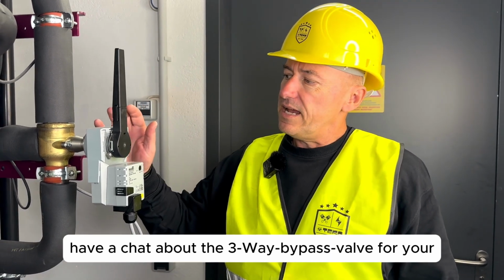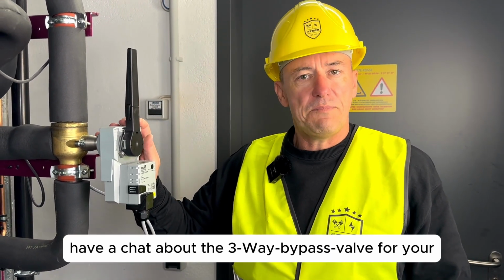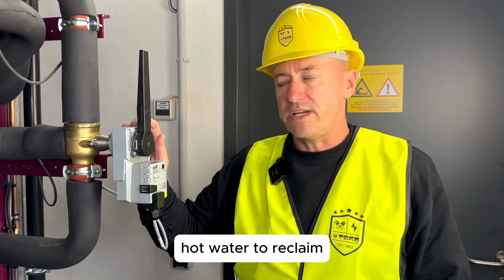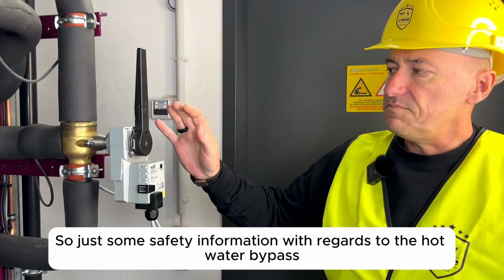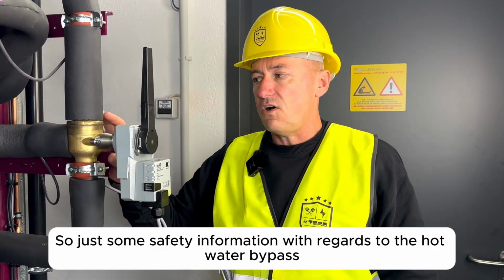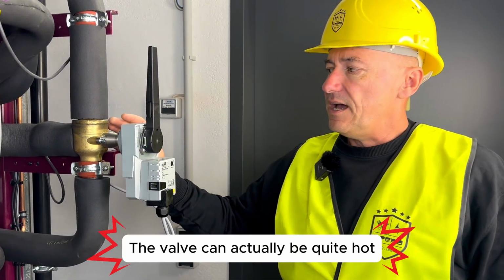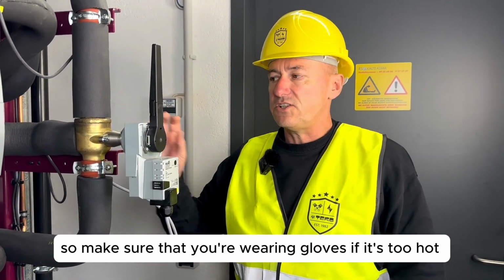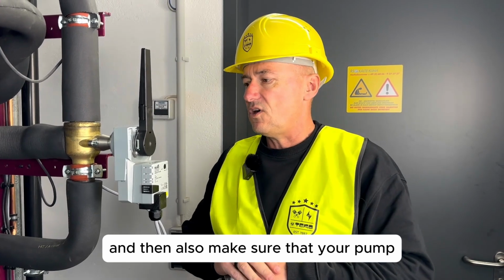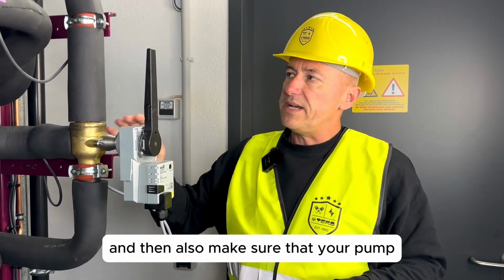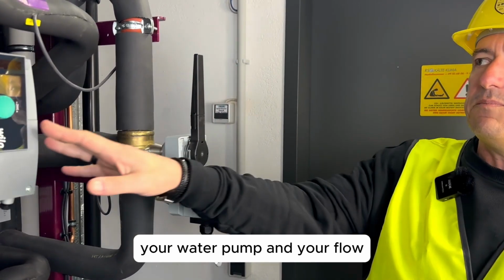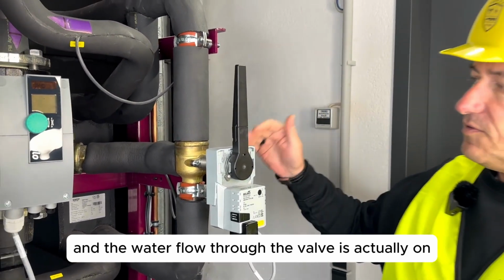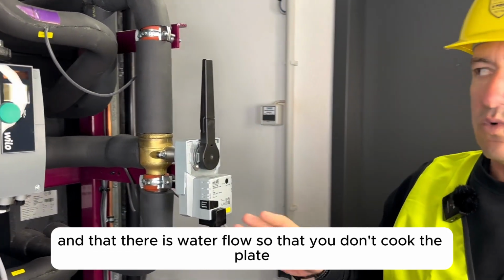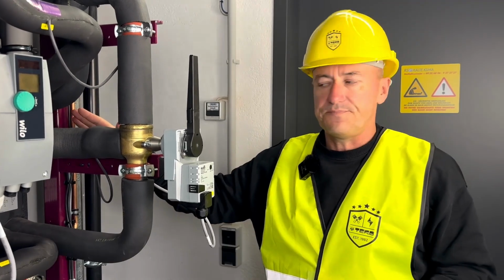Today we're going to have a chat about the three-way bypass valve for your hot water reclaim. So just some safety information with regards to the hot water bypass valve. The valve can actually be quite hot, so make sure that you're wearing gloves if it's too hot. And also make sure that your water pump is on and that there is water flow through the valve so that you don't cook the plate.